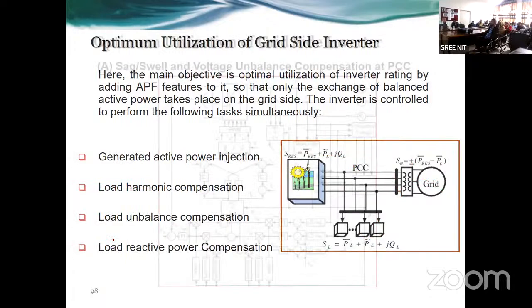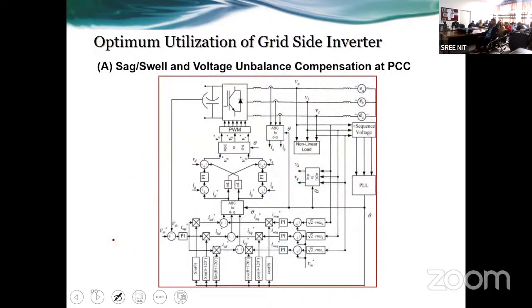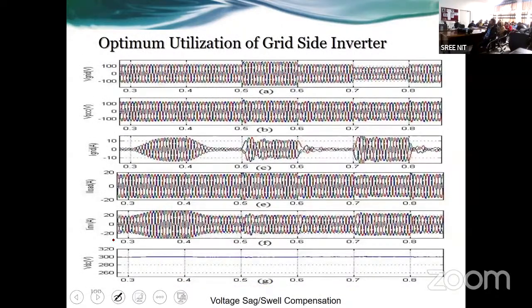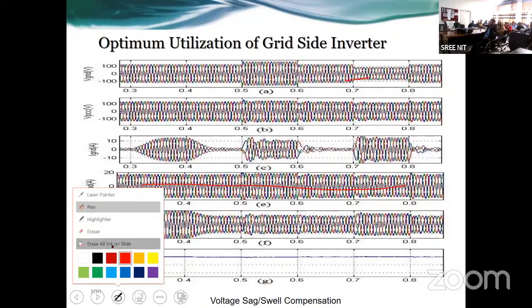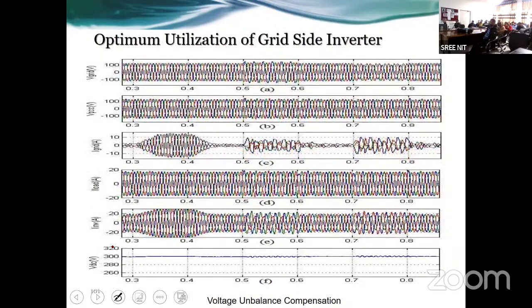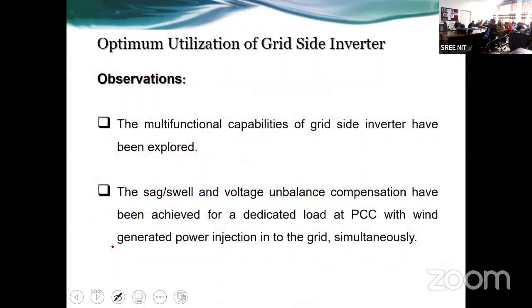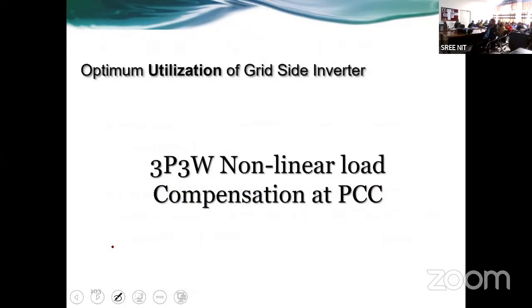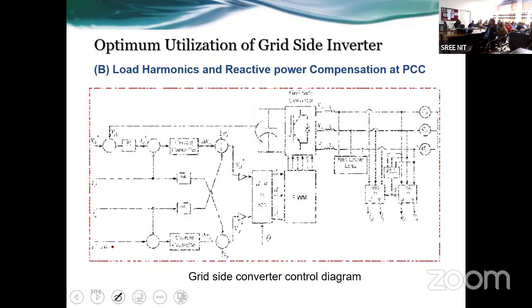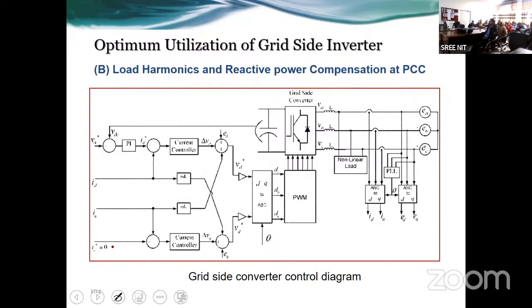And this was the voltage compensation which I have done with the help of this. So this is the grid voltage fluctuation, but the nearby load is fed at almost constant voltage. I will show you the harmonic part also. This is the unbalanced part which I have controlled. So this is the three-wire nonlinear system. This is the control part.